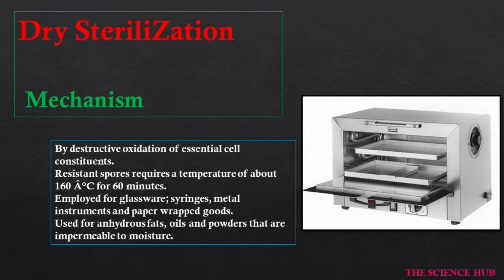Dry sterilization works by destructive oxidation of essential cell constituents. Resistant spores require a temperature of about 160 degrees Celsius for 60 minutes. Employed for glassware, syringes, metal instruments and paper-wrapped goods. Used for anhydrous fats, oils and powders that are impermeable to moisture.